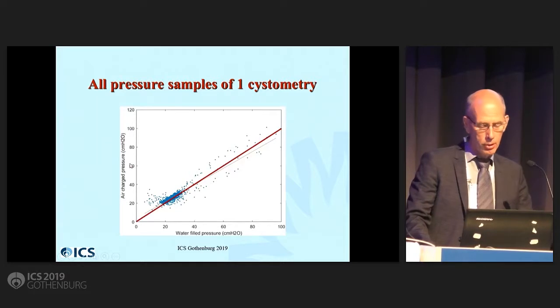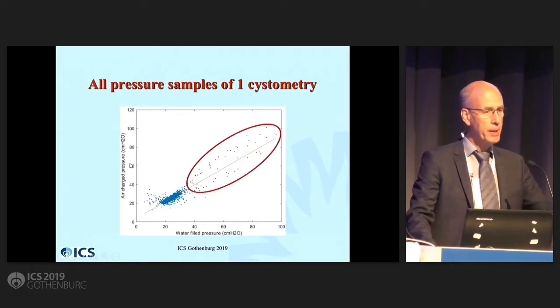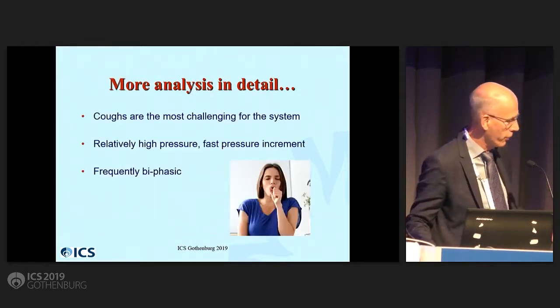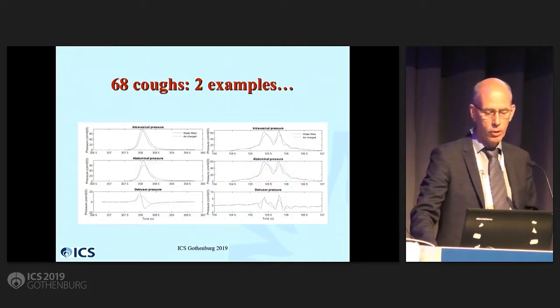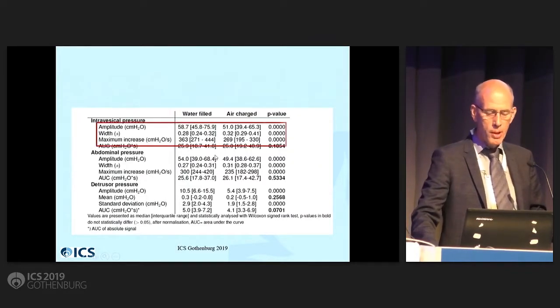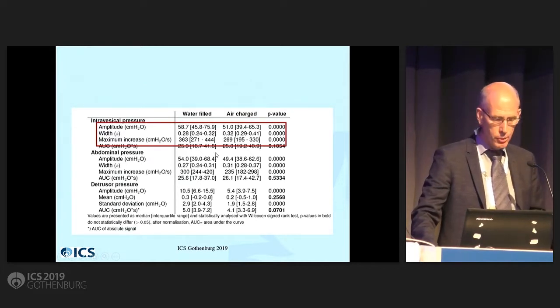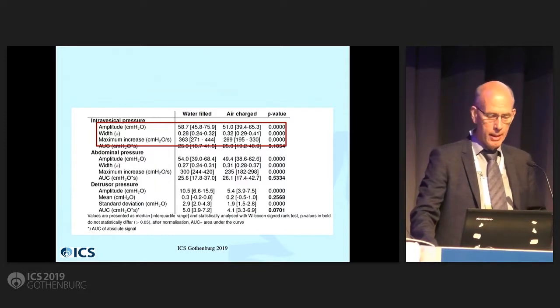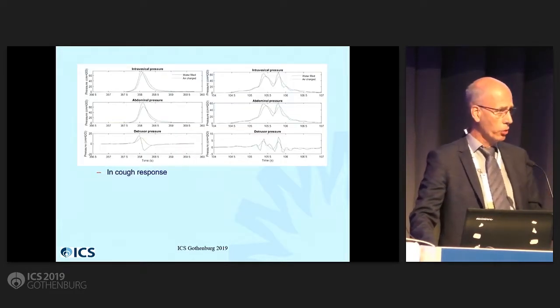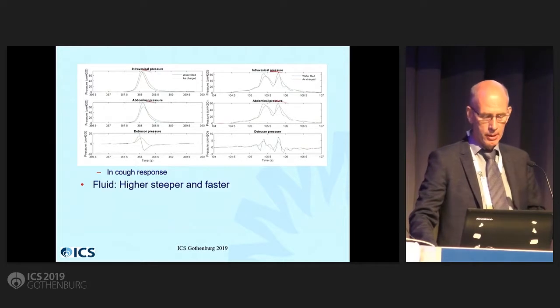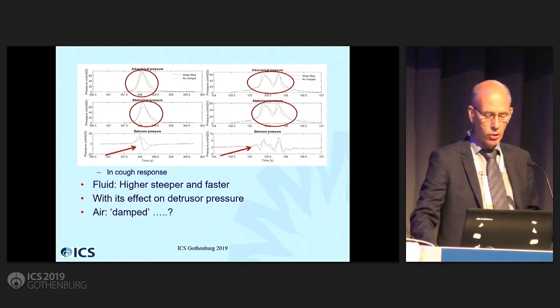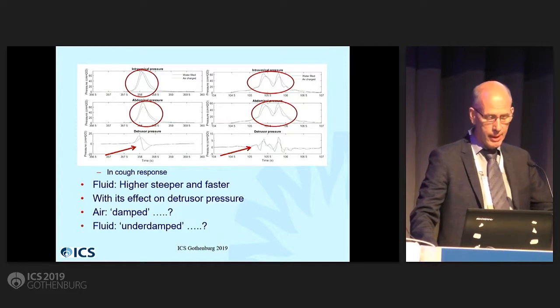Although there is a very high correlation, the high pressures are the most challenging — those are the coughs. So we did specific analysis of the coughs. Here are two coughs out of 68. You see the similarities, but we saw significant differences in the amplitude and the width. However, the area under the curve is very similar, meaning the total amount of pressure measured is very similar. Fluid is slightly steeper and slightly faster in its effect on the detrusor pressure. You could question whether air is damped or fluid is underdamped.